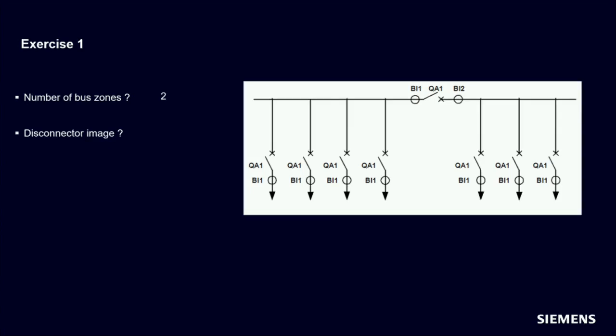Do we need a disconnector image? Please remember, when do we need a disconnector image? We need a disconnector image when it is possible via disconnectors to assign a feeder current to different bus zones. And this is definitely not possible here. We have no busbar disconnectors at all. Each feeder is directly assigned to a dedicated bus zone. So we don't need a disconnector image in this case.